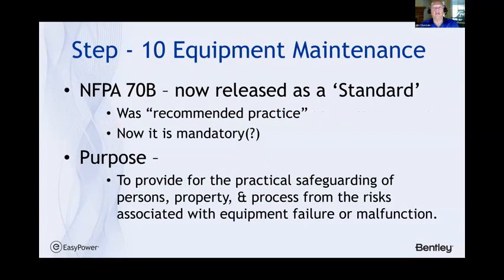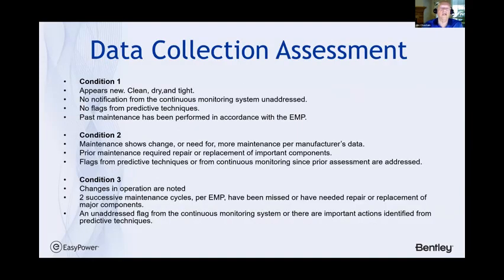And then step 10 is make sure you have equipment maintenance that's included or referred to now by NFPA 70B, which has been recently released as a standard. It used to be recommended practices. Now it's mandatory. And the purpose is to provide for electrical safeguard to persons and property and process from risks associated with equipment failure or malfunction. And what it gives us are descriptions of different levels or conditions that can be accepted and evaluated during the data collection assessment. And here's 3 reference points that are general in nature, but could be modified for particular applications.